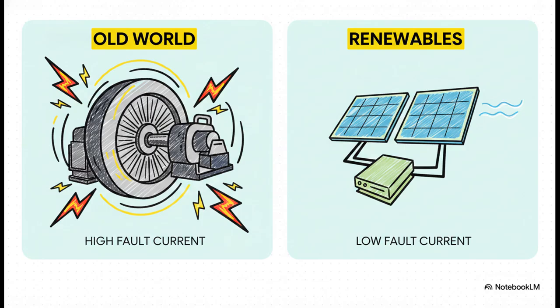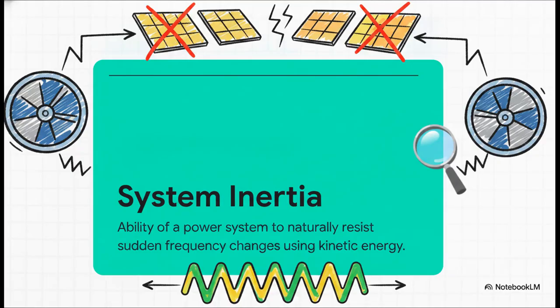Traditional synchronous generators, think of those massive steam turbines in a nuclear or coal plant, have incredible heavy rotating mass. That gives them natural mechanical inertia. Plus, they naturally output high fault currents, which makes triggering safety relays super easy. But renewables like solar panels, they are what we call inverter-based resources. They connect to the grid through power electronic converters. They have absolutely zero inherent physical mass spinning around, meaning zero physical inertia, and they produce a vastly reduced fault current. So why does that matter?